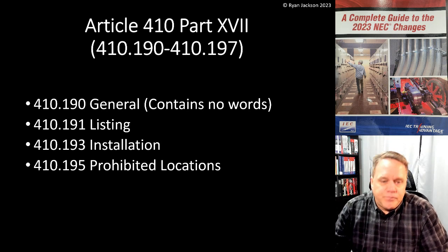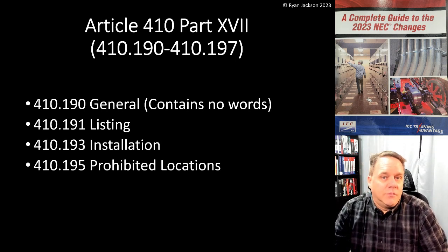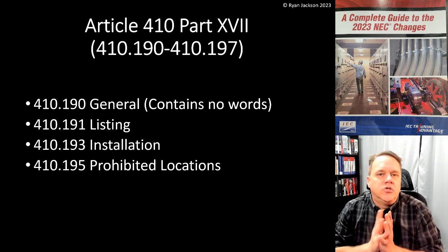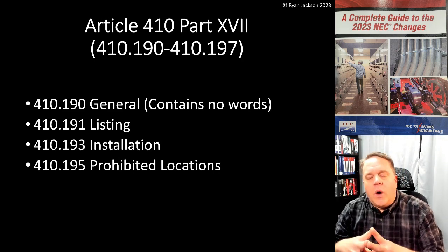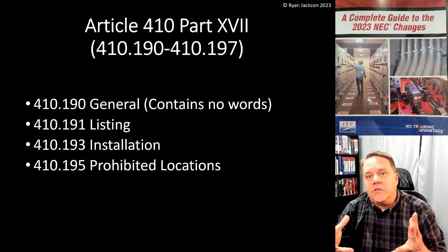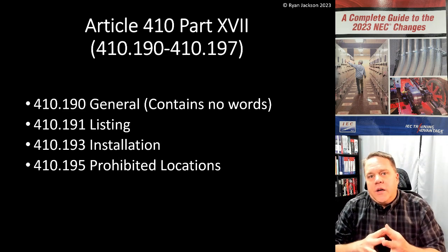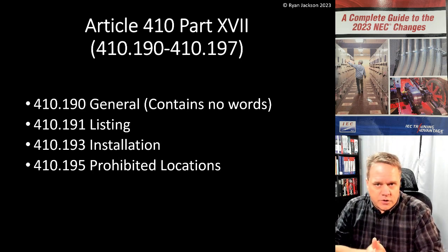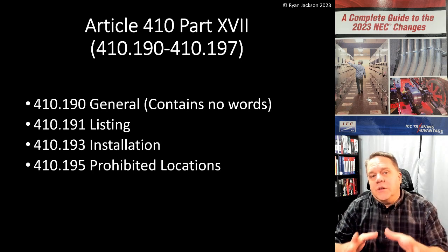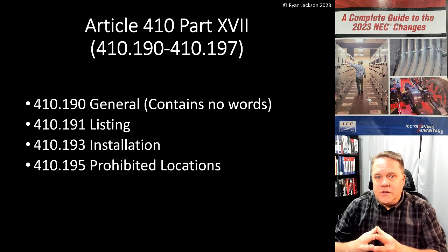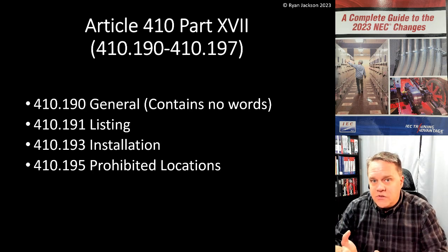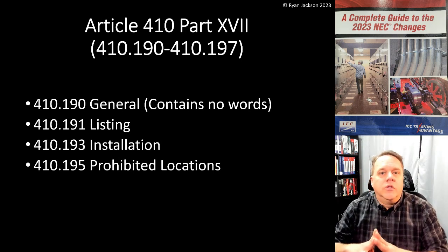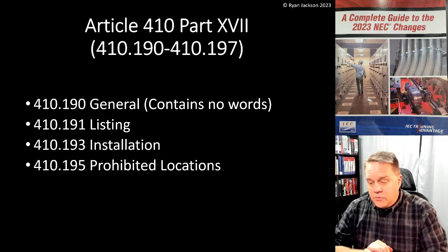Section 410.195 actually has some important language, though again it mostly says to follow instructions. Germicidal irradiation luminaires are UV lighting luminaires designed to kill germs — and with COVID we're going to see more of these installed, both residential and commercial. If the luminaire says don't use it in occupiable space, or that it's intended only for use when the building is unoccupied, we need to follow those instructions.